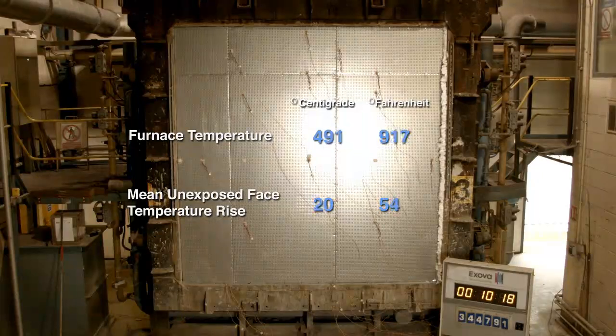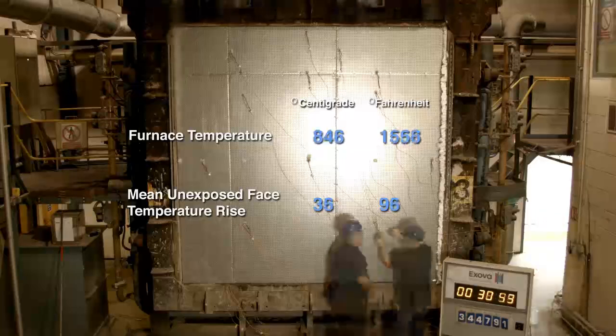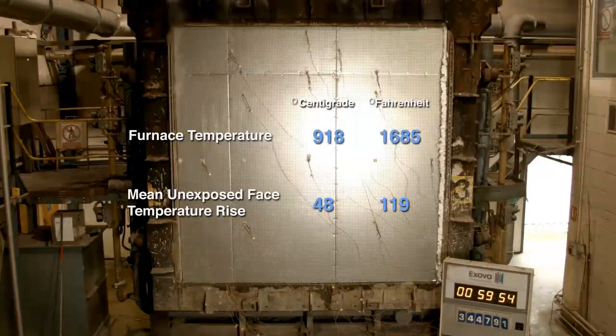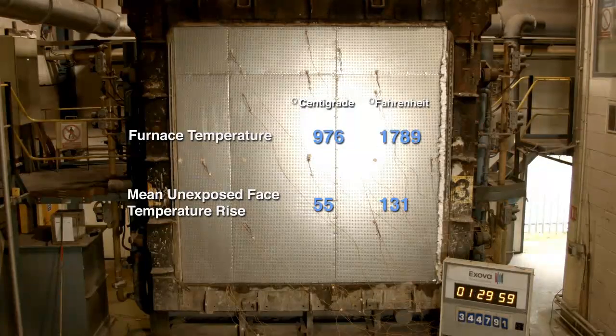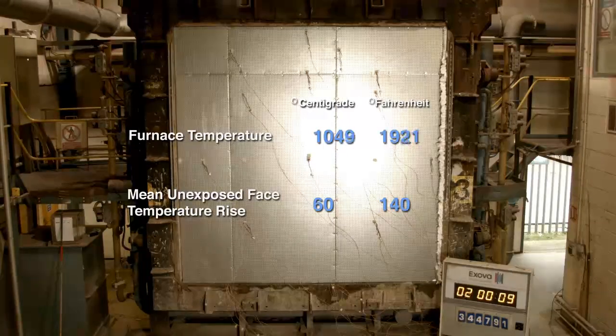This test is designed to represent a fire in a building. Thermocouples within the furnace will measure the temperature to ensure it follows the cellulosic fire curve according to the standards. Other tests have shown that Durasteel can also withstand exposure to a hydrocarbon fire — a more onerous test designed to represent fires in the oil and gas industry.